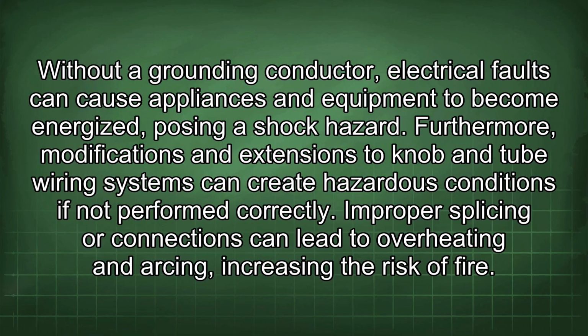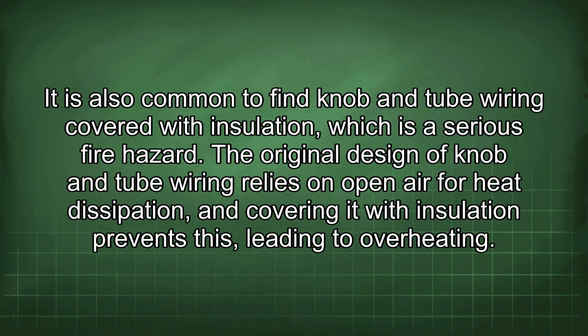Furthermore, modifications and extensions to knob and tube wiring systems can create hazardous conditions if not performed correctly. Improper splicing or connections can lead to overheating and arcing, increasing the risk of fire. It is also common to find knob and tube wiring covered with insulation, which is a serious fire hazard. The original design of knob and tube wiring relies on open air for heat dissipation, and covering it with insulation prevents this, leading to overheating.